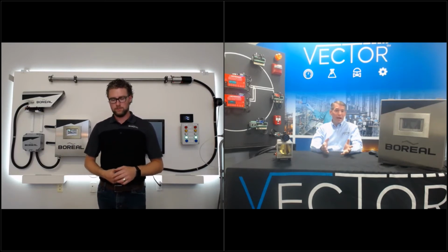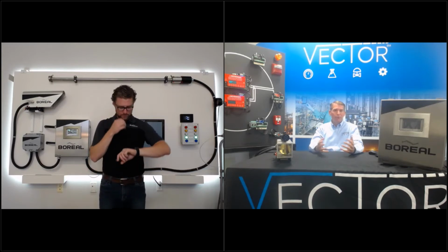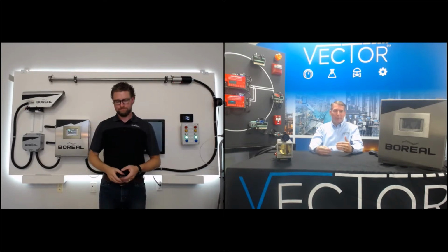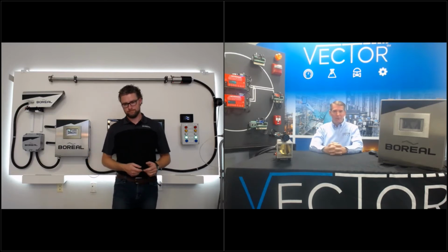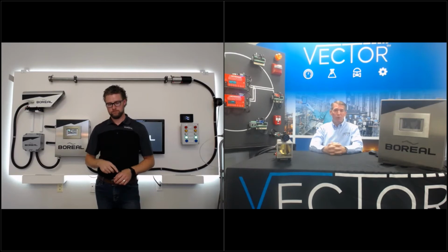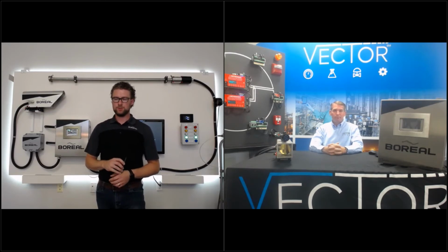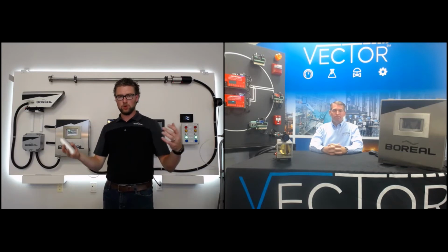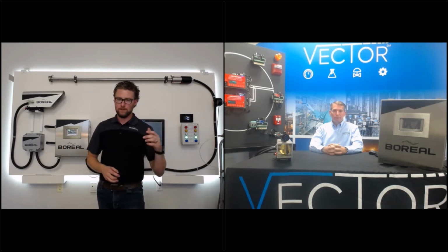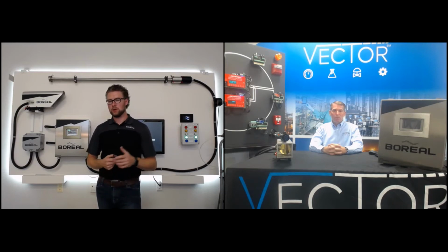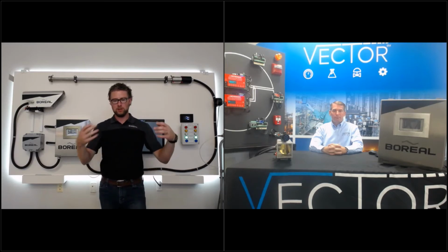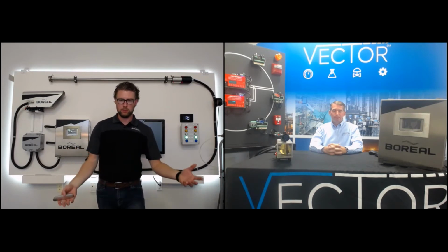One thing there too, Kyle, is that this system is fully configurable from an alarm set point standpoint. So even if you have those smaller leaks that maybe you don't want to alarm on, your alarm thresholds can be set higher than that, but it gives you the ability to maybe go and provide some maintenance to an area before it becomes more severe. Absolutely. So if you don't necessarily want to alarm at the lower level leaks, there could be maintenance call indications or other items that your reliability or operations team can look at and repair those small leaks before they become large ones.